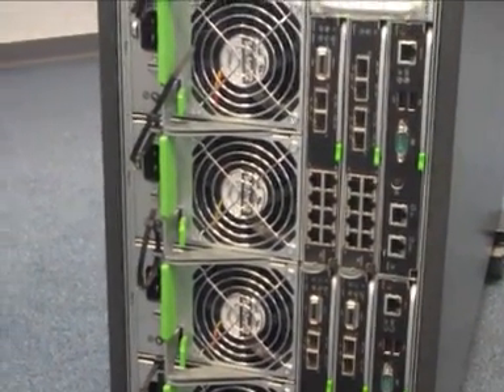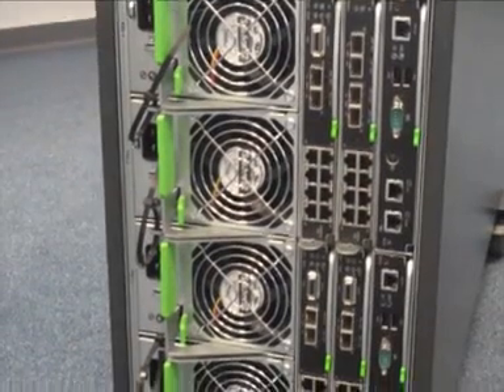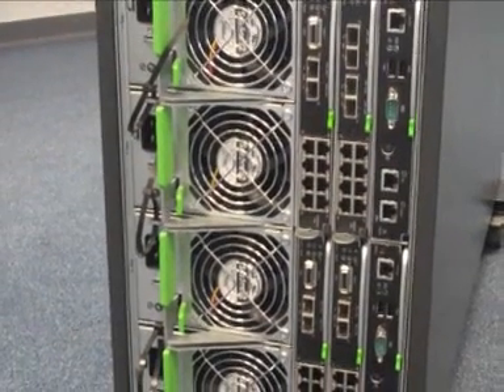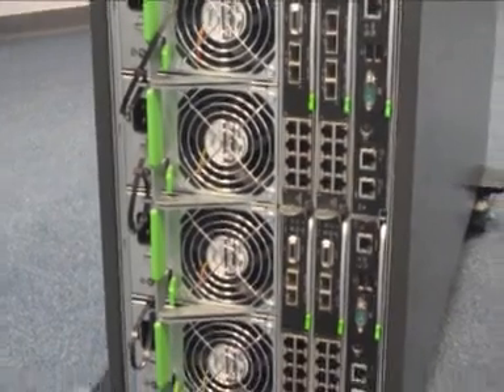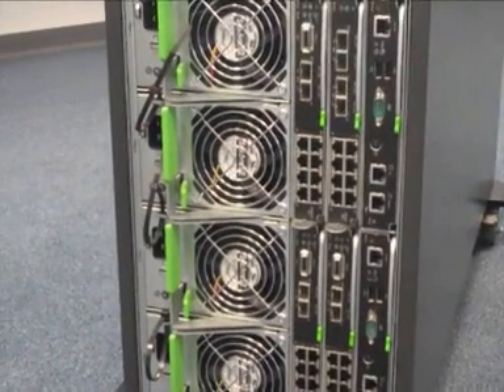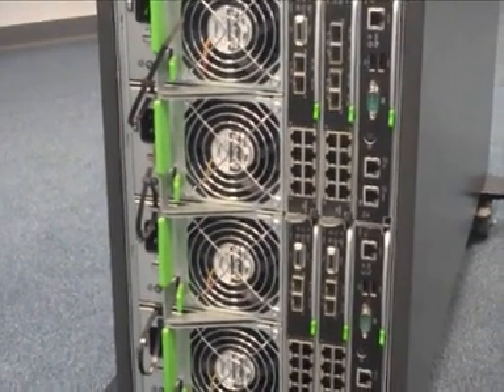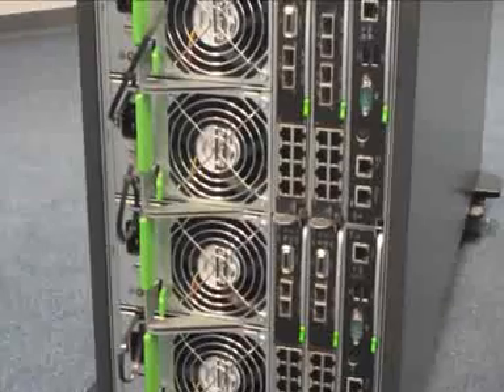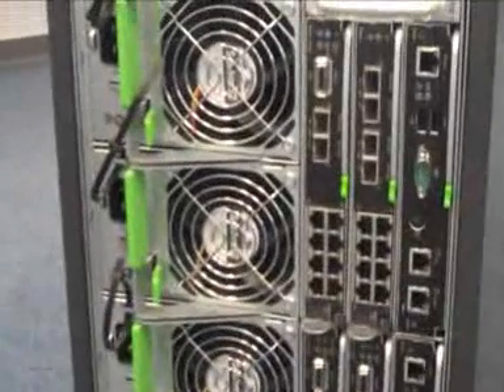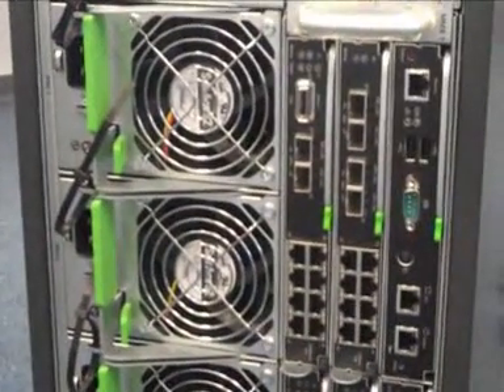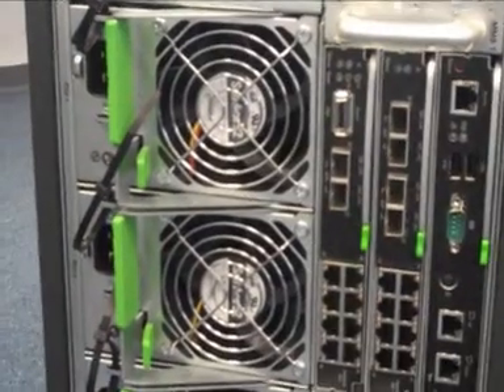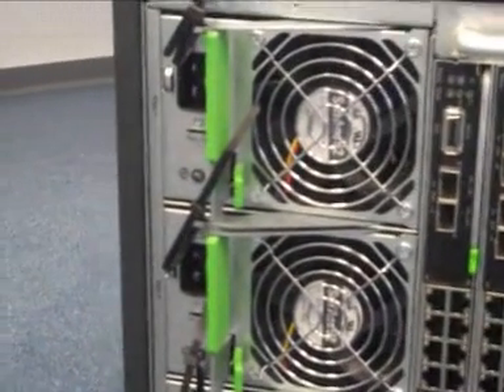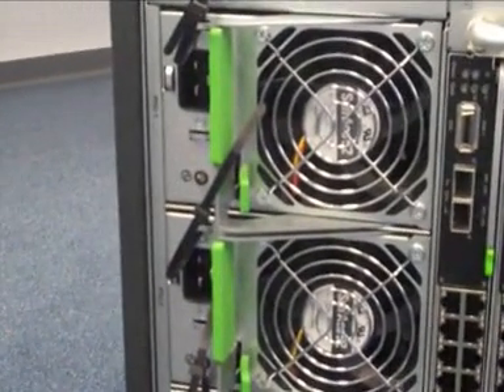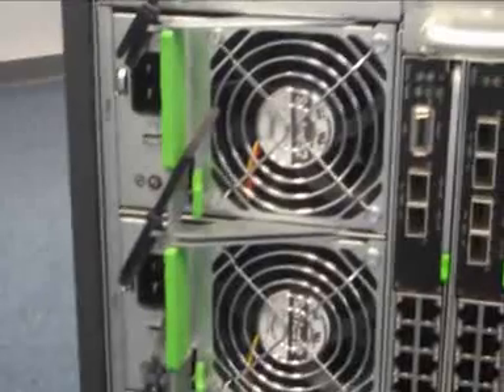So as I told you before, we do have a lot of different power modes. So that means we can run, for example, a so-called dynamic mode. That means non-used power supplies are automatically running in a standby mode to have a better efficiency on the remaining ones. So for example, one of these power supplies has a power efficiency of more than 92%. That's very state-of-the-art, this power efficiency here.